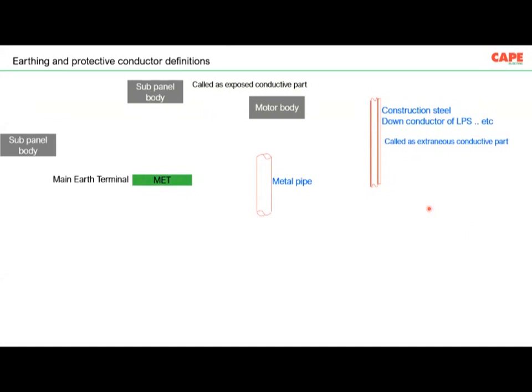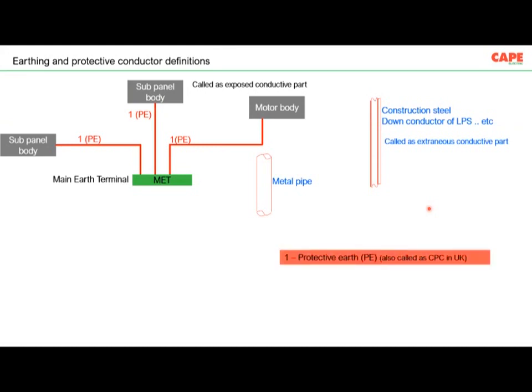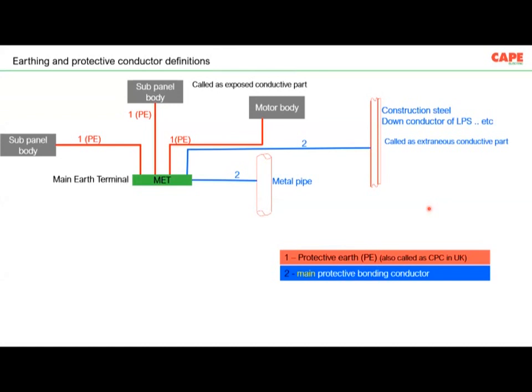You have to have an equipotential bonding bar, which is called the MET, or a bus bar, which offers a potential very close to the earth potential, zero potential, which is going to be the reference for this entire building. Now, all the exposed conductive parts are connected to the MET through, I have given a red color. The actual color is green and yellow, but just for identification, I gave a red color. These are called protective earthing conductors. The extraneous conductive parts, such as a metal pipe and other metal parts, are connected to the MET through the blue colored wire, which is called a protective bonding conductor.